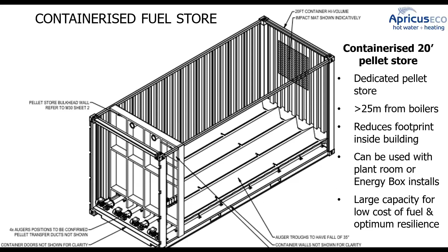So where are we up to now? All right, how much? So we looked at the Palmerston North example, and that was 130 kilowatts with an external pellet store, and we said that it was about 160,000 installed, finished, including building works. Now, if we look at what we can do with a 20-foot container, we can go up to 130 kilowatts of output in one container, and including the fuel store already plug and play, no need for buffering. Just put the flow and return pipework out there and off it goes.